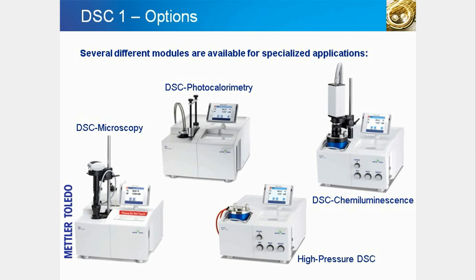The DSC-1 instrument can be fitted with optional accessories for specific applications. The slide shows different DSC modules offered by Mettler-Toledo: DSC microscopy, DSC photocalorimetry, high-pressure DSC, and DSC chemiluminescence. DSC microscopy is used to visually observe sample effects in the crucible and hence aid interpretation of the DSC curve. The visual information allows you to identify solid-solid transitions, to distinguish between overlapping processes such as melting and decomposition, to study the shrinkage behavior of fibers or films, or to identify the cause of an artifact in DSC curves.